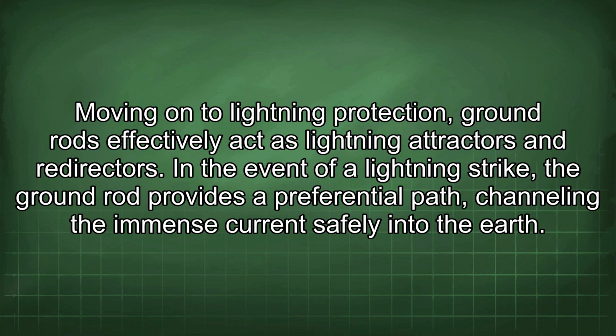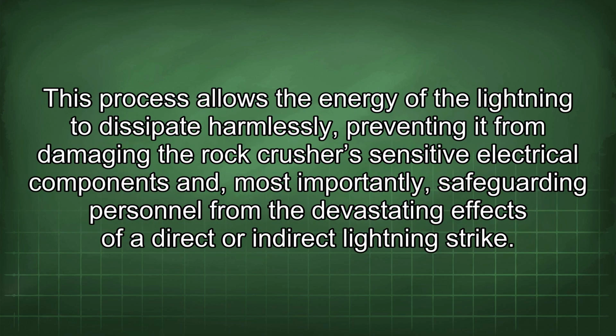Moving on to lightning protection, ground rods effectively act as lightning attractors and redirectors. In the event of a lightning strike, the ground rod provides a preferential path, channeling the immense current safely into the earth. This process allows the energy of the lightning to dissipate harmlessly, preventing it from damaging the rock crusher's sensitive electrical components and, most importantly, safeguarding personnel from the devastating effects of a direct or indirect lightning strike.